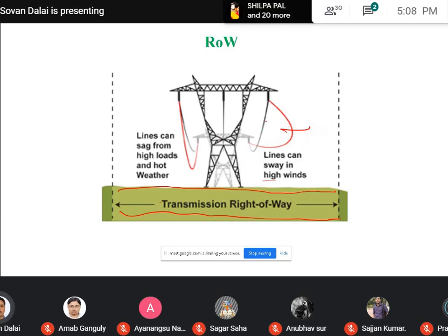Also, due to the weight, you see one thing at the bottom portion: suppose here is one tower and here is another tower, and in between there is no tower. If you connect a conductor or a rope between the two points, some portion will look like this. This is called the transmission line sag. So we have to maintain a certain gap distance from the earth to the bottom portion of this conductor. When designing a transmission line, we have to consider the sag, so that the line does not touch the ground.